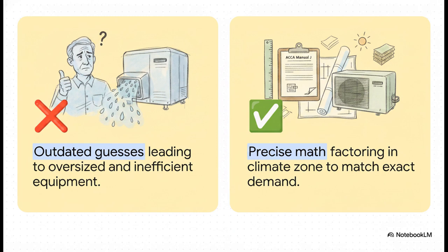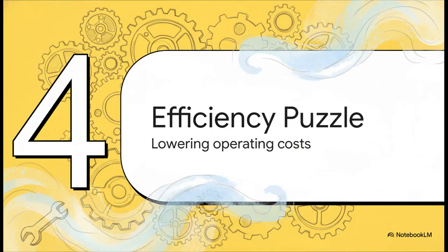The old way relied on rules of thumb, basically just guesses, that usually resulted in oversized equipment. An oversized unit cools the house too fast without actually removing the humidity, leaving you with a cold, clammy home. The professional standard is the ACCA Manual J load calculation. It uses precise math, factoring in your exact climate zone, insulation levels, even window area, to perfectly match your home's actual demand.